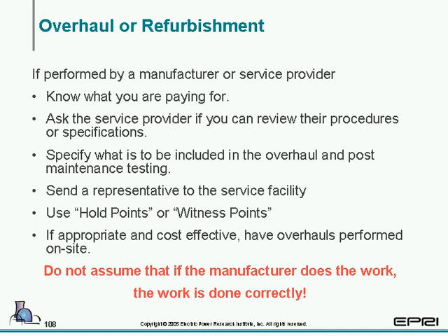Moving on to overhaul and refurbishment. If performed by a manufacturer or service provider, know what you are paying for. Know what the manufacturer is going to do to your circuit breaker. Ask if you can review their procedures, or a lot of times the manufacturer will give you specifications or a summary of what they're going to do to your breaker. If you can, specify what is to be included in the overhaul and possibly post-maintenance testing. If you can, send a representative, use witness points or hold points.